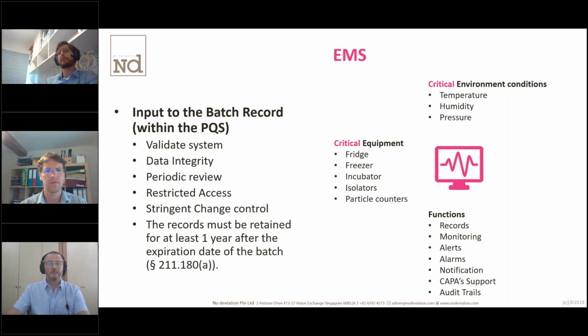And from the time they were captured, during all those years, you need to have that data life cycle, and you need to be able to trust those data. So the EMS will look at everything which is critical, which touches the quality. So it's critical environmental conditions, and you can add those based on your process needs. It's critical equipment that we can plug into an EMS system, which are the fridge, freezer, incubator, isolator, particle counter. And the function is really to record, monitor, alert, alarm, give some notification, and support the corrective and preventive action and investigation. And we need to have an audit trail so that we can know who did what, when and where, for all the data recorded.